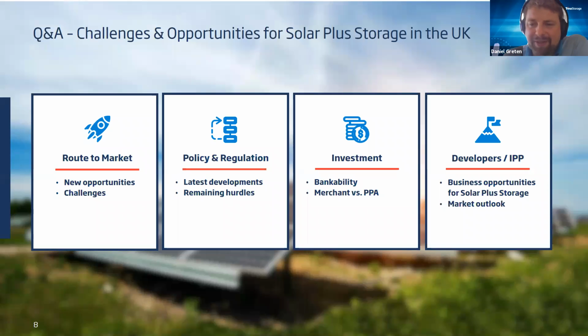Yeah, I think it's interesting that the question comes actually from existing standalone storage, because typically we're being asked the other question, right? It's the other way around. So you have an existing PV plant, and what do you need to do actually to add storage to it, right? I think just to come to that question probably first, because it's a more common case, the main thing here is you're reducing options, because typically going to a DC coupled system then doesn't make too much sense. So you would rather look into an AC coupled solution after, and then it comes mainly to the setup actually on the feeder. So it's what kind of substation do we have, and how can we best integrate the battery there?